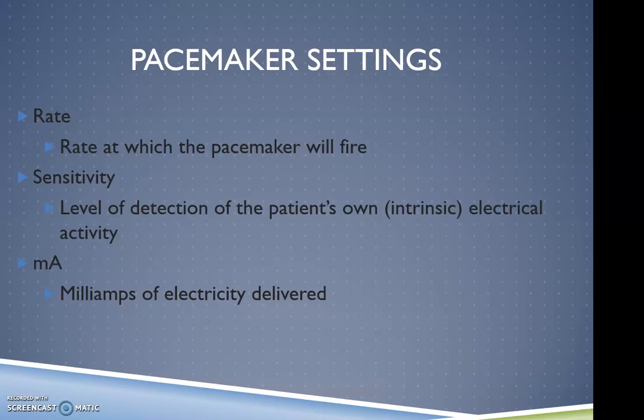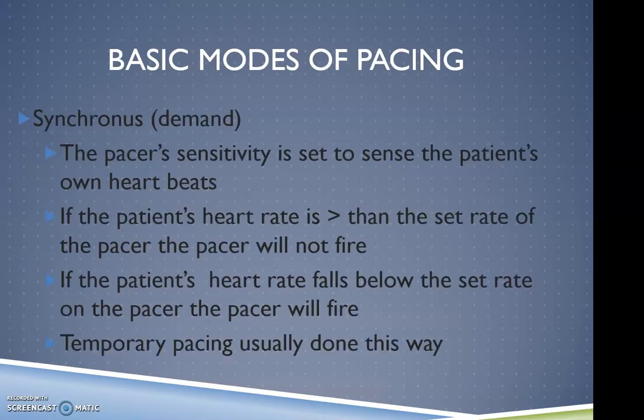That's the rate we set that we want the pacemaker to fire. The sensitivity. How sensitive do we want it to what the patient's doing? Do we want it to be very sensitive so that it only works when the patient's own conduction system's not working? Or do we not care and we just want to pace when we want to pace? And then the mA is the amount of electricity that we have to deliver to get the mechanical capture that we're looking for. Some basic modes.